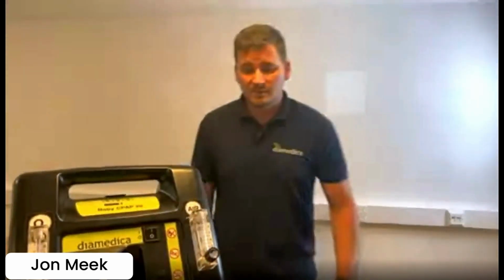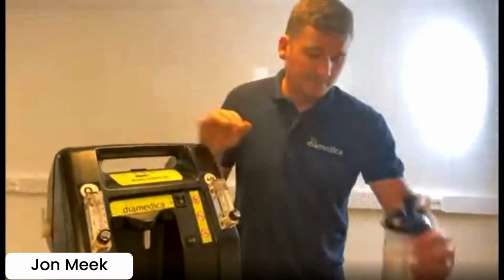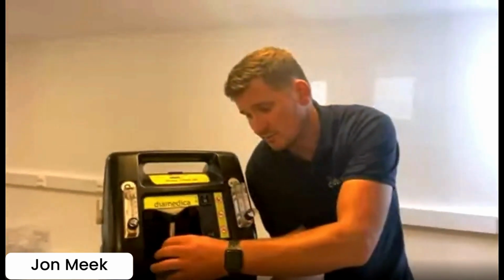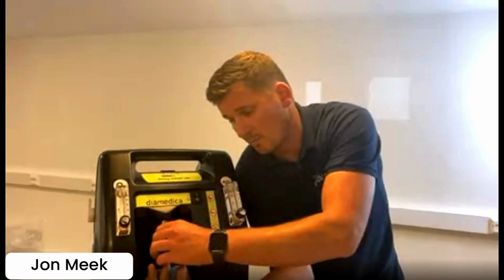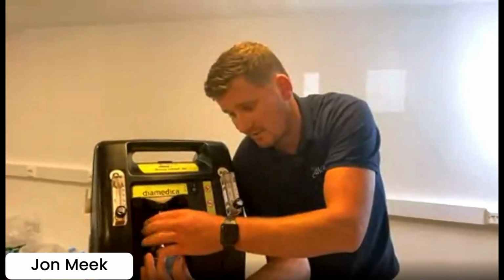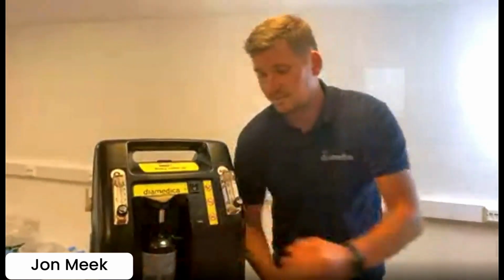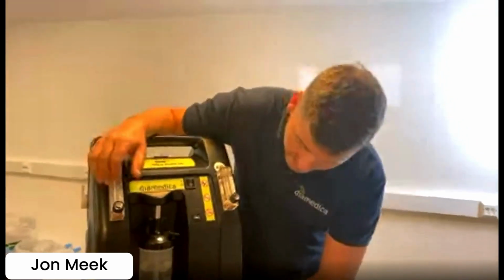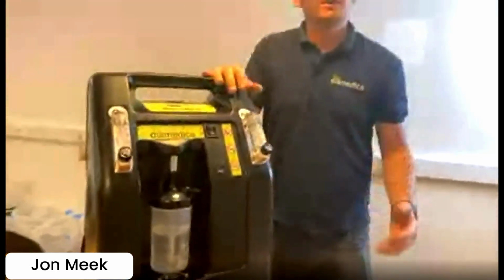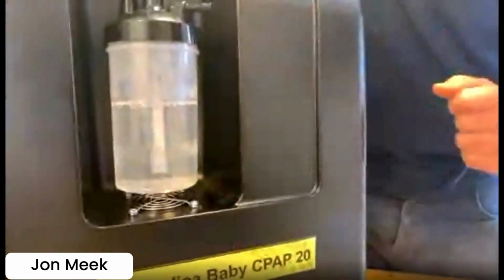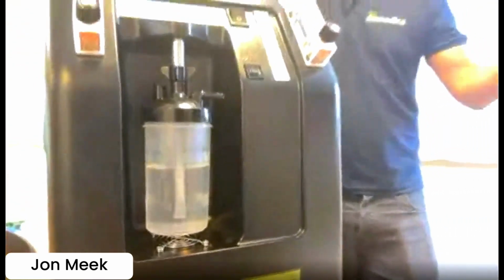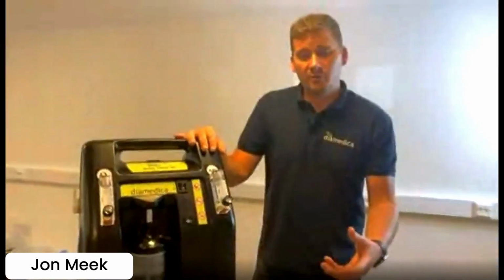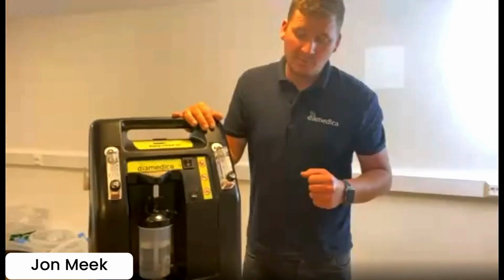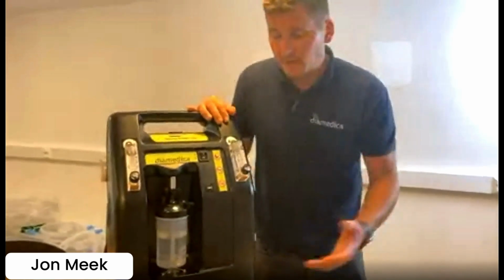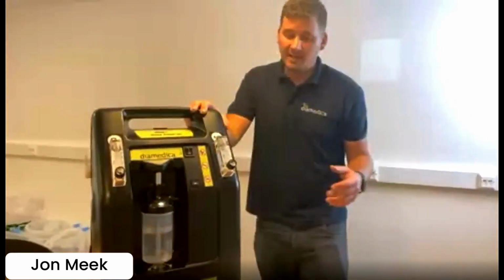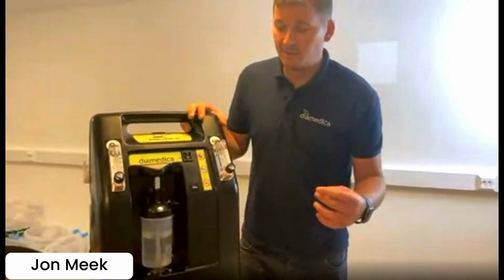So what we have, first of all, as we said, is a humidifier bottle to provide humidification, which is really important to provide a warm oxygen and air mixture with humidification, not a dry mixture. You can see underneath, there was a grill. There is a slight flow rate of warming air underneath, which will warm the humidifier bottle. On the air set, it's not controlled. On this one, we've redesigned it to improve the warming by controlling the flow onto the bottom of the humidifier bottle, allowing the flow rate to ensure the warming to the correct level, between 31 and 36 degrees.